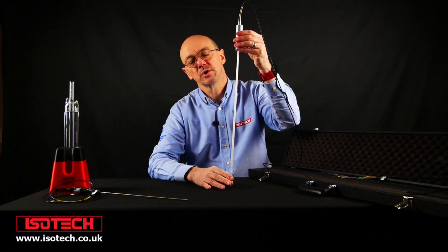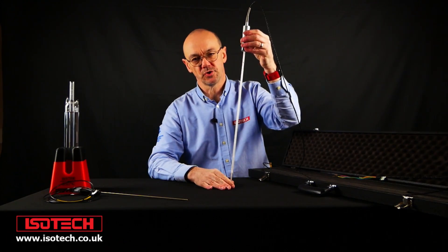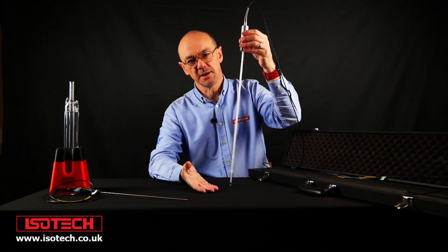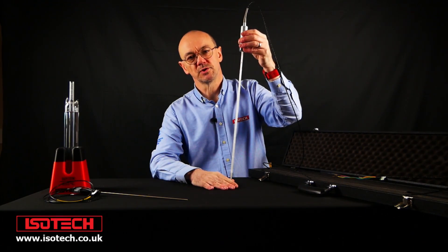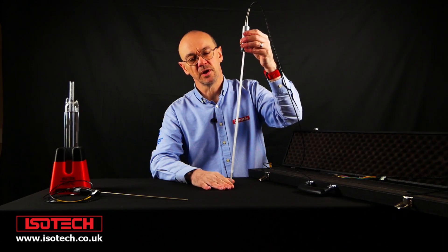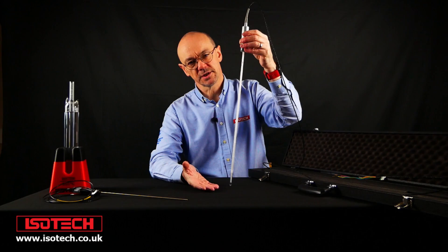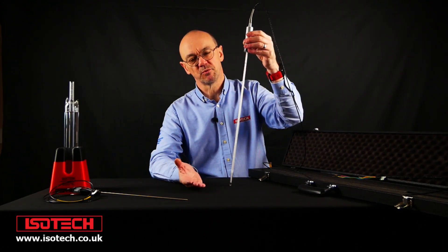At Isotech, we always point out that when you're using an SPRT, it's really important to consider the application. SPRTs need good immersion depth, and if you can't immerse the thermometer deeply enough, it's not the thermometer to use. These devices are very fragile — they're not suitable for use in industry or in portable applications. They really belong in the calibration lab, where they can be handled very carefully. Whilst the SPRT has the lowest uncertainty of any resistance thermometer, that doesn't necessarily make it the best thermometer for all applications.